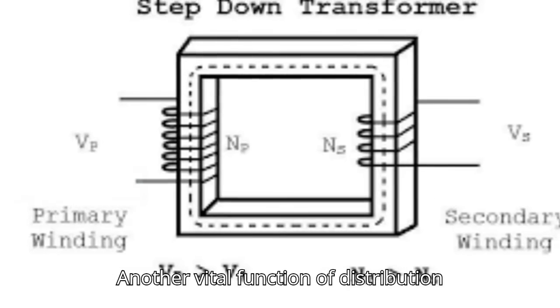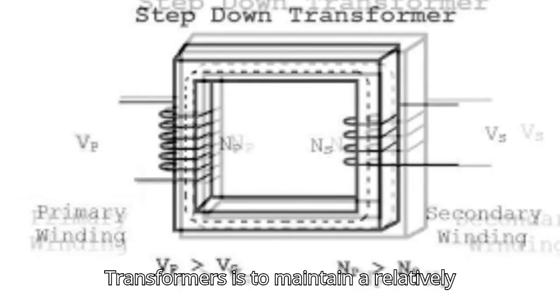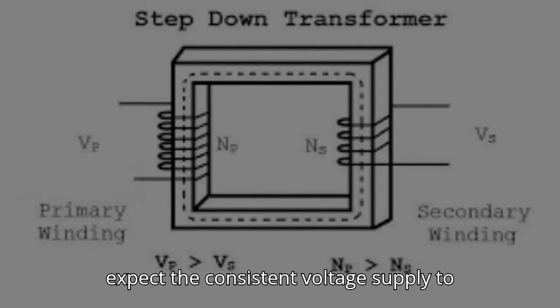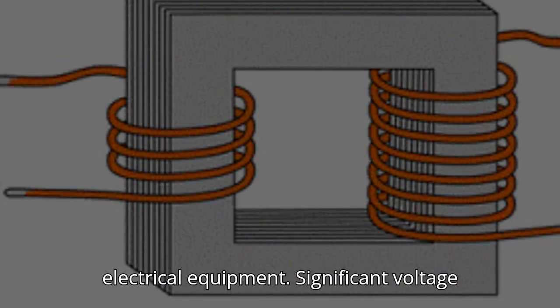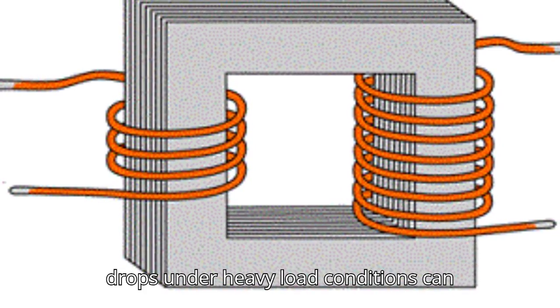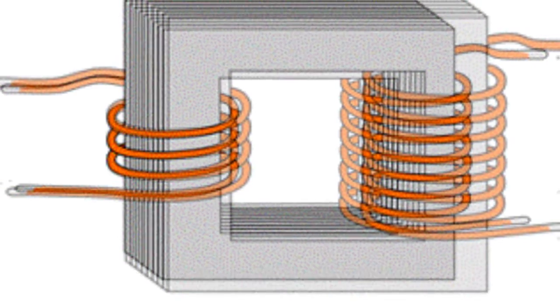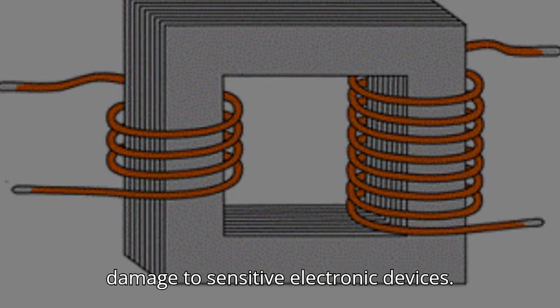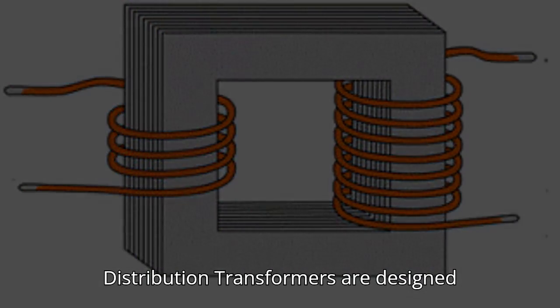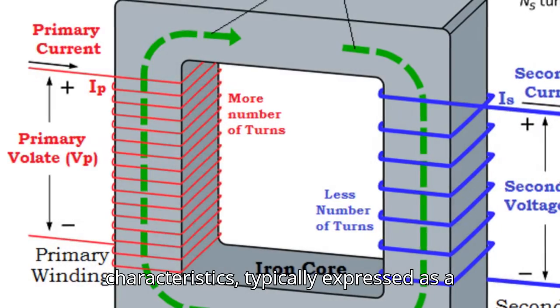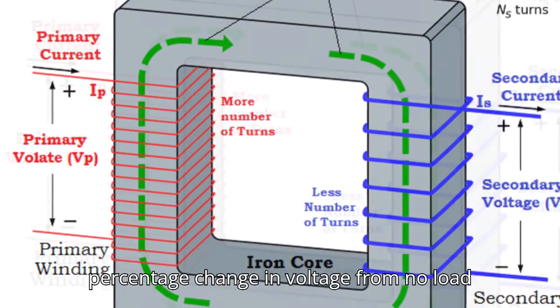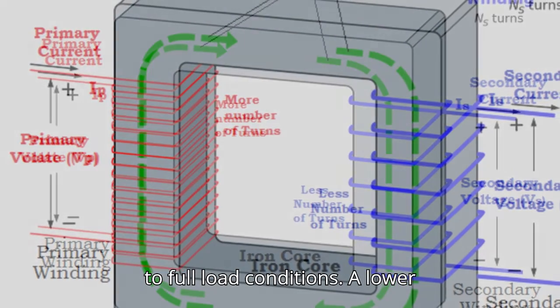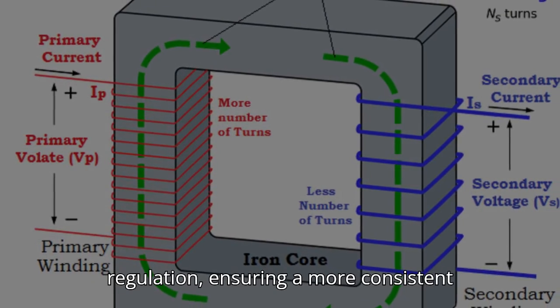Maintaining stable output voltage, voltage regulation. Another vital function of distribution transformers is to maintain a relatively stable output voltage despite the variations in the load. Consumers expect a consistent voltage supply to ensure the proper operation of their electrical equipment. Significant voltage drops under heavy load conditions can lead to malfunctioning appliances, reduced lighting intensity, and potential damage to sensitive electronic devices. Distribution transformers are designed with good voltage regulation characteristics, typically expressed as a percentage change in voltage from no load to full load conditions. A lower percentage indicates better voltage regulation, ensuring a more consistent and reliable power supply to the end users.